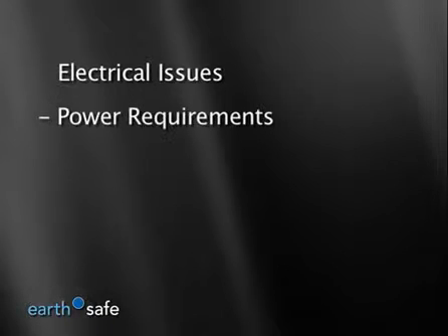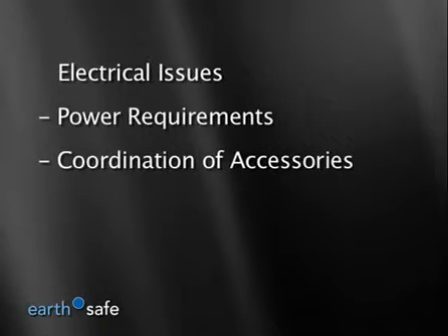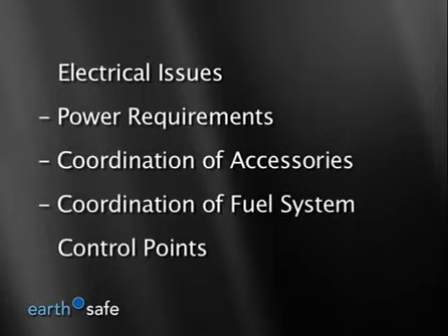Electrical issues are power requirements for fuel system equipment, coordination of generator accessories such as day tanks and filters, and the coordination of fuel system control points needed for generators and switchgear. Building management system coordination is a determination of the points to be monitored and the communication protocols. Fire alarm and security system issues involve coordination of any required fuel system control points for these systems.